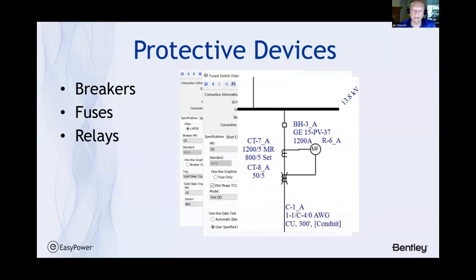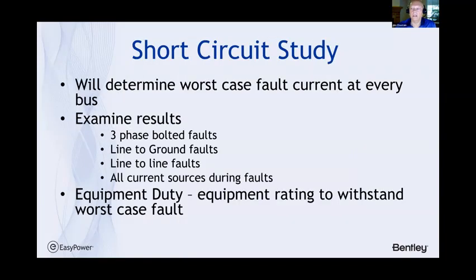Now, once that's completed, the first order of events is called the short circuit study. And that's necessary because it will determine the worst case fault current at every bus in the system. Now, most software packages will be able to accomplish this without too much effort once the data has been entered and is accurate. So what it produces is a three-phase bolted fault, a line to ground fault, again at every bus in the system, and then the line-to-line faults, including all current sources during the fault.